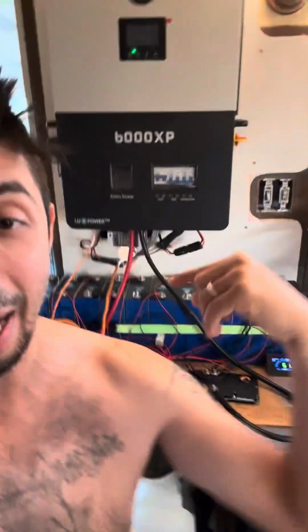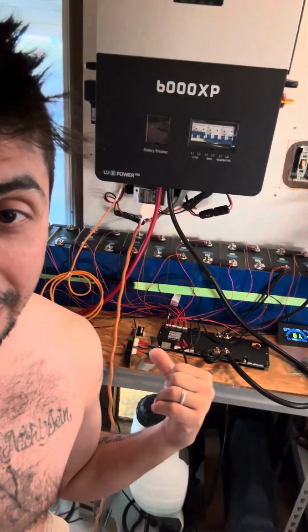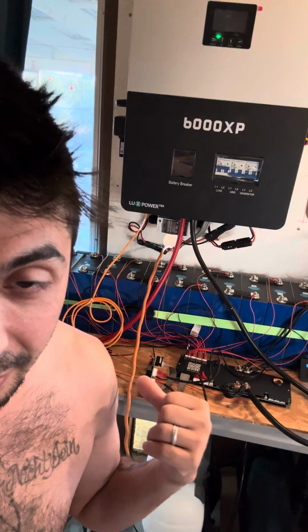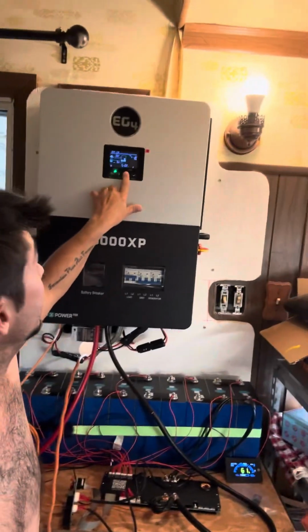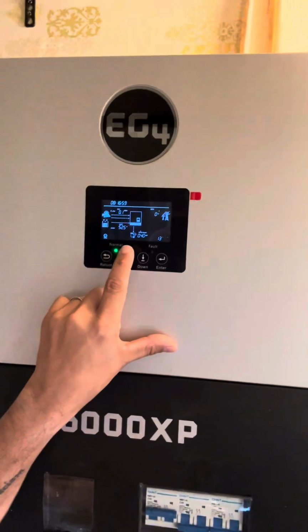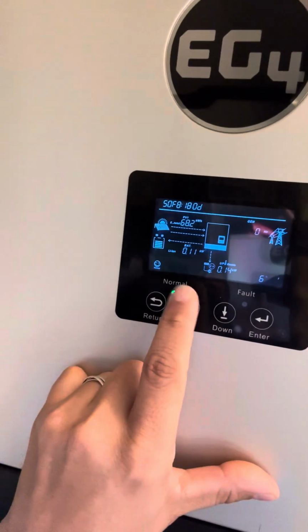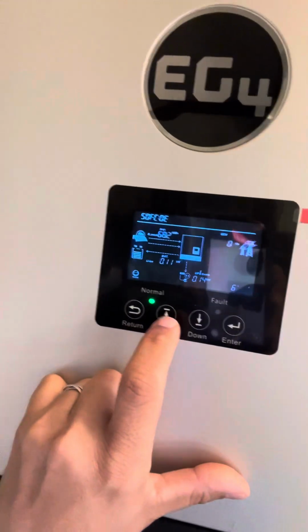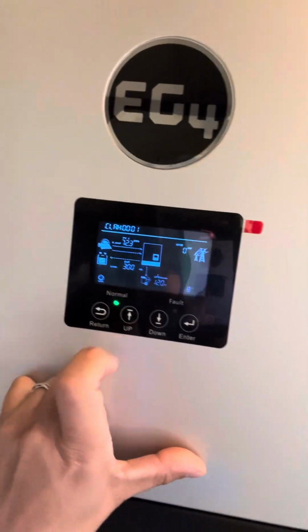Now instead of dumb mode, I put it back in communication mode. So now the Ethernet is running, and now they're talking, and now this thing reads 52.5 volts, 61%, which matches my gauge. It's currently charging at 0.1 kilowatt, and it's got a 300 amp hour capacity.